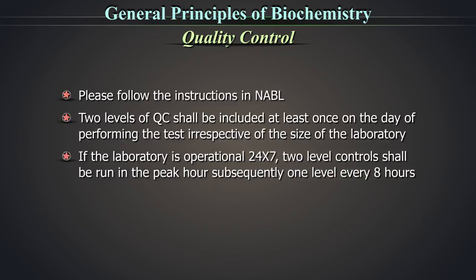If the laboratory is operational 24-7, two level controls shall be run in the peak hour, subsequently one level every 8 hours.